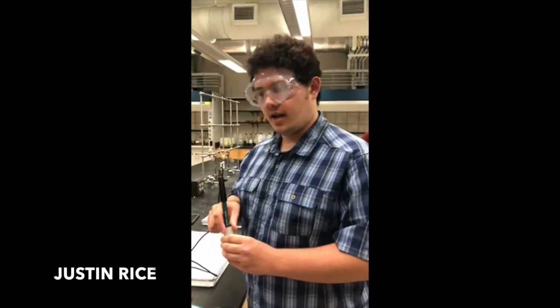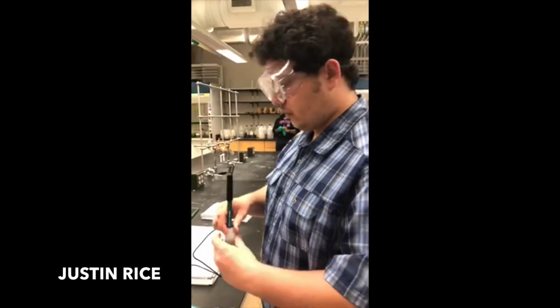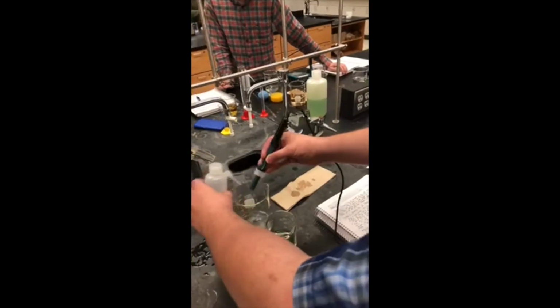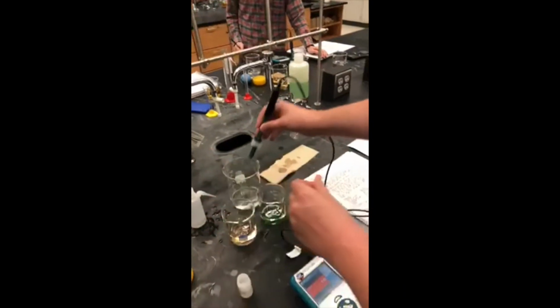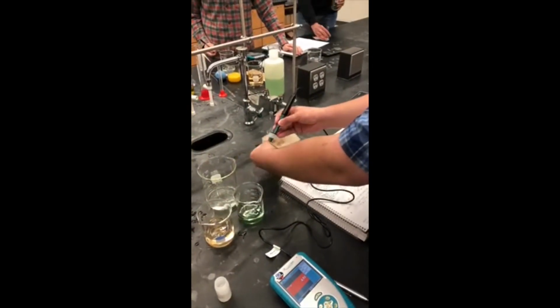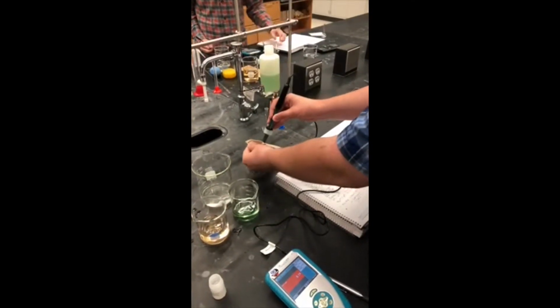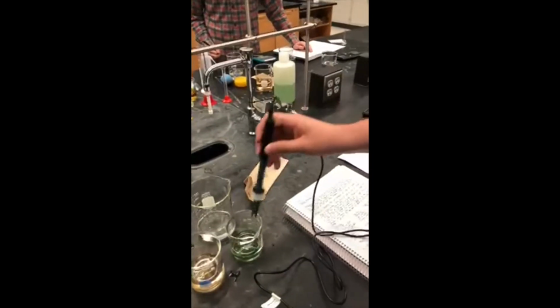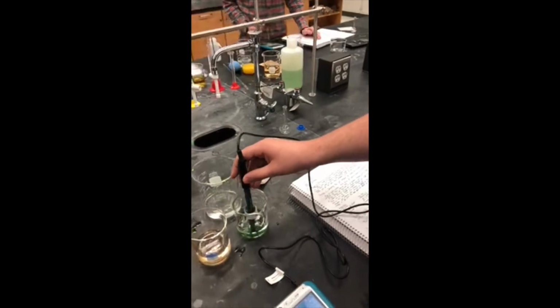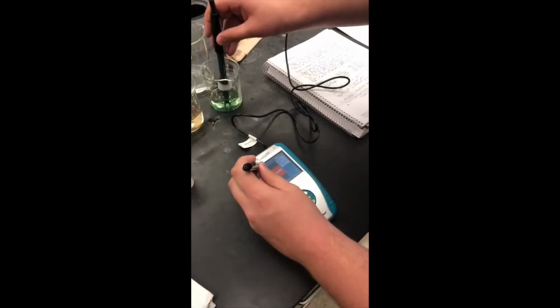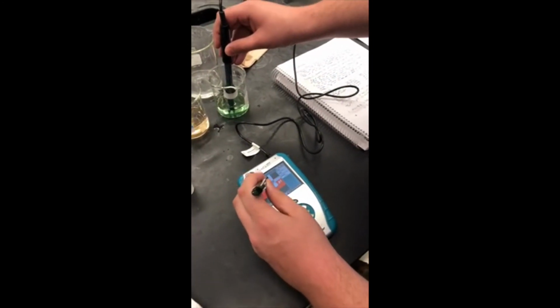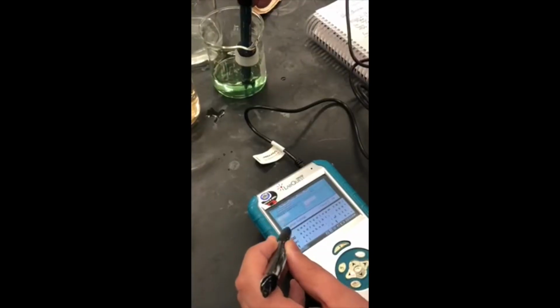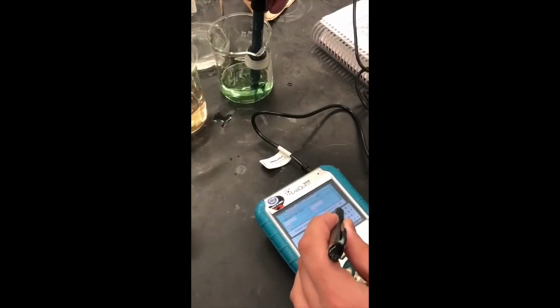I'm going to be performing a calibration of orange juice. I'm going to rinse that off with some distilled water. Get that water off, make sure nothing messes with our reading. As we put it into the pH 7 solution, or buffer, I'm going to go to Sensors, Calibrate now, and we're going to set this one to 7.